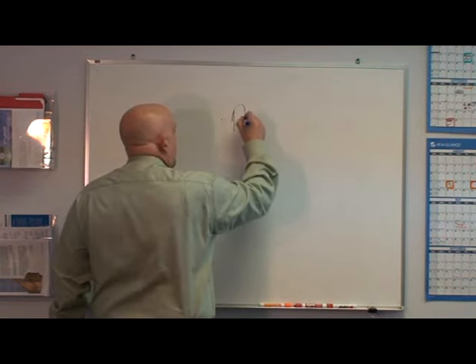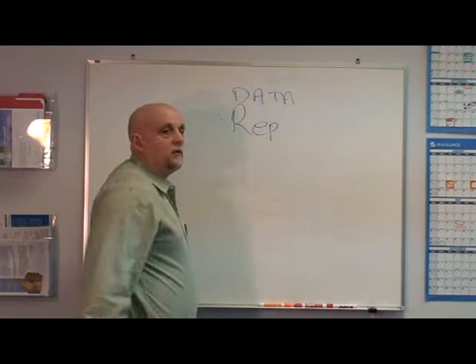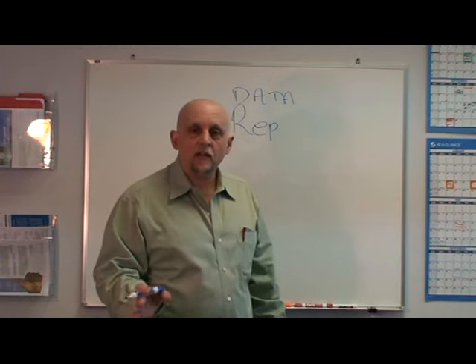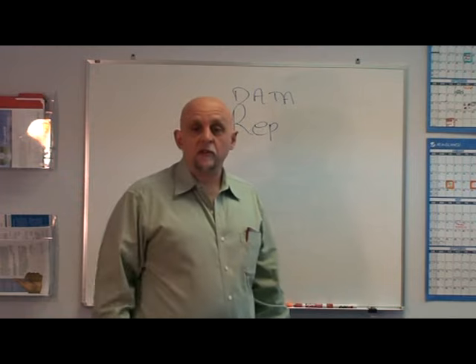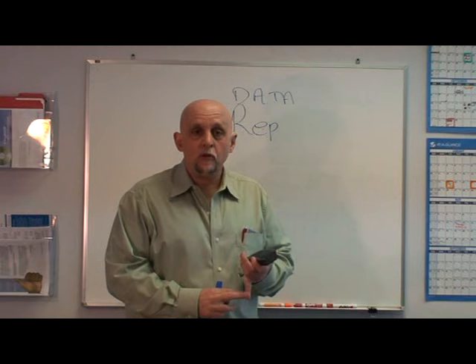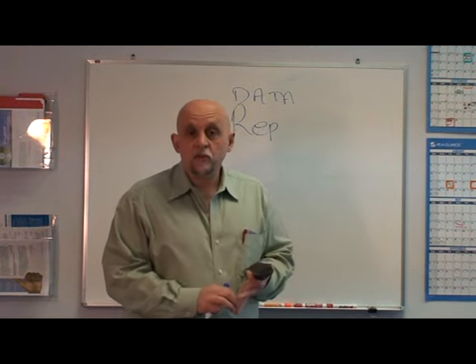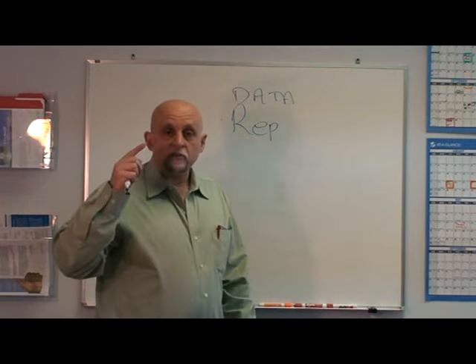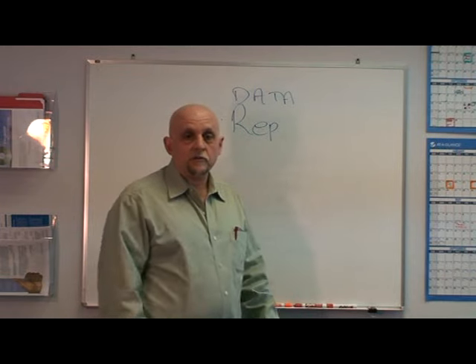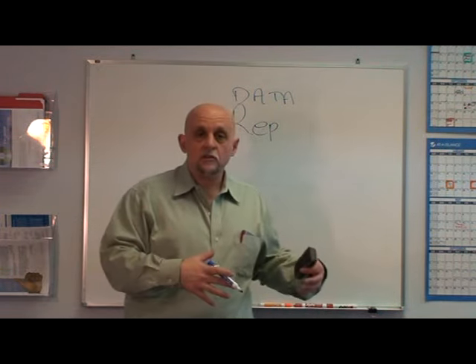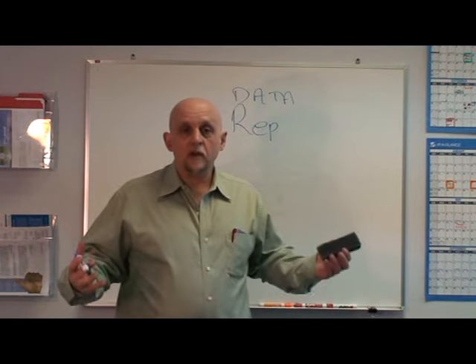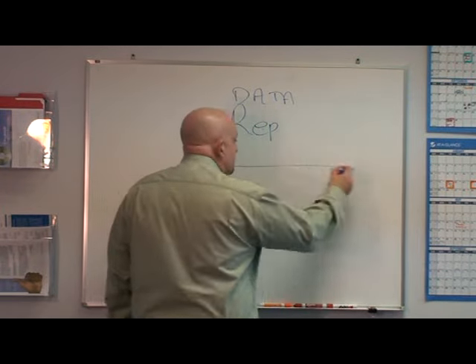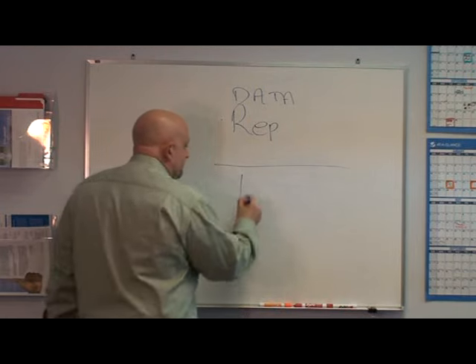The third thing that we want to know about Modbus: data representation. How is data represented in Modbus? Two ways, either registers and coils. What are we talking about data representation anyway? Whenever you have any kind of network device, everybody wants to know, how do I talk to that device? How do I access the data in that device? Whether it be some kind of IO lines, whether it can be some kind of analog value like a temperature, whether it's the status of a valve. Well, in Modbus things are represented in two ways, by 16-bit unsigned registers, and by single bit coils. And so every device has some set of registers and some set of coils. Could have both, could have one, could have the other. Doesn't matter, it's up to the designer of the device to pick.